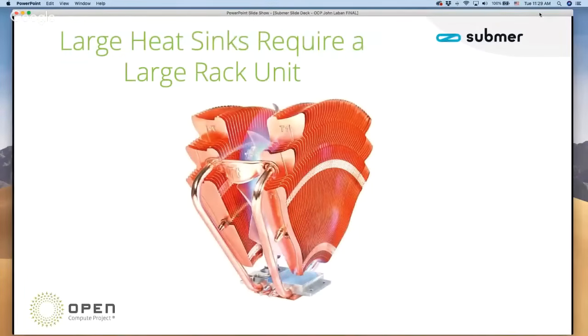Another thing that happens with OCP is we use higher rack units. The good thing about a higher, deeper rack unit is we can fit big heat sinks, and with a big heat sink you get the heat off the CPUs much more efficiently using less energy. That's another reason we like them to be bigger.